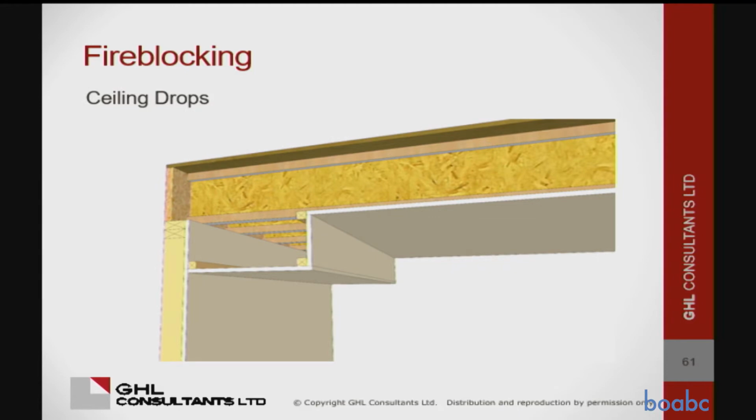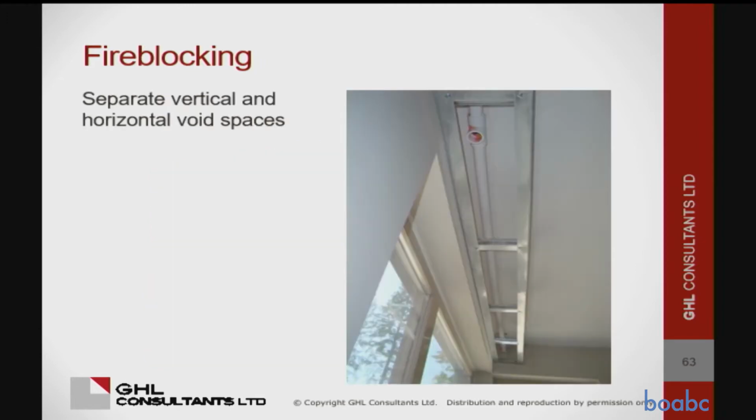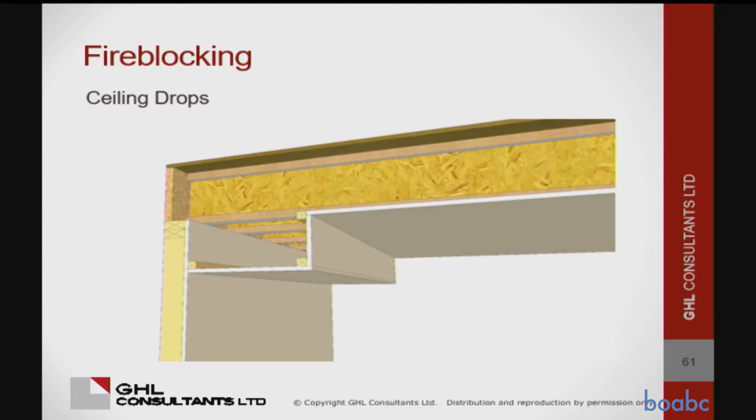So we had a long, interesting discussion in the office about these slides the other day. Can you do this? Because now is that bulkhead part of the floor? Or can you do this? And now that bulkhead's part of the wall? Or do you need to do both? I mean, that's typically what you see, right? Somebody drywalls the whole thing and then they build their bulkhead out of steel studs so they don't have to sprinkler anything inside it.